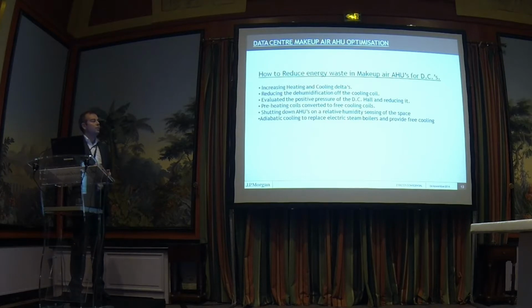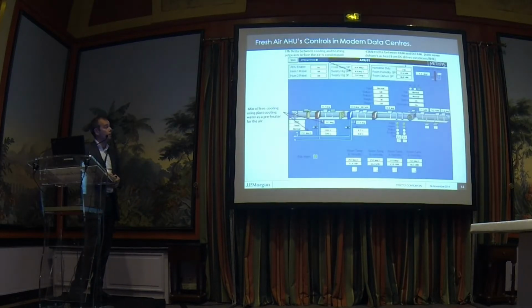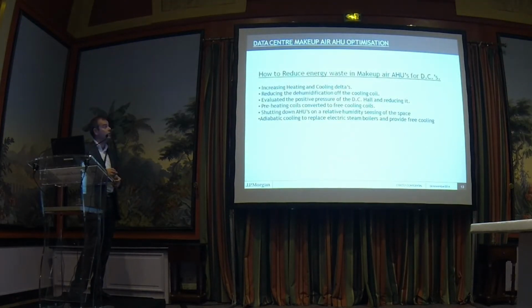I've seen AHUs for fresh air make-up for DCs running at a 10 degree supply, which is just ludicrous, because you're throwing this air into a pressurised box at high level into a 30-degree environment. Why are you doing that? I can throw it in at 28 degrees, still achieve cooling, but I'm not using energy to do it. So, reducing the heat and cooling delta.